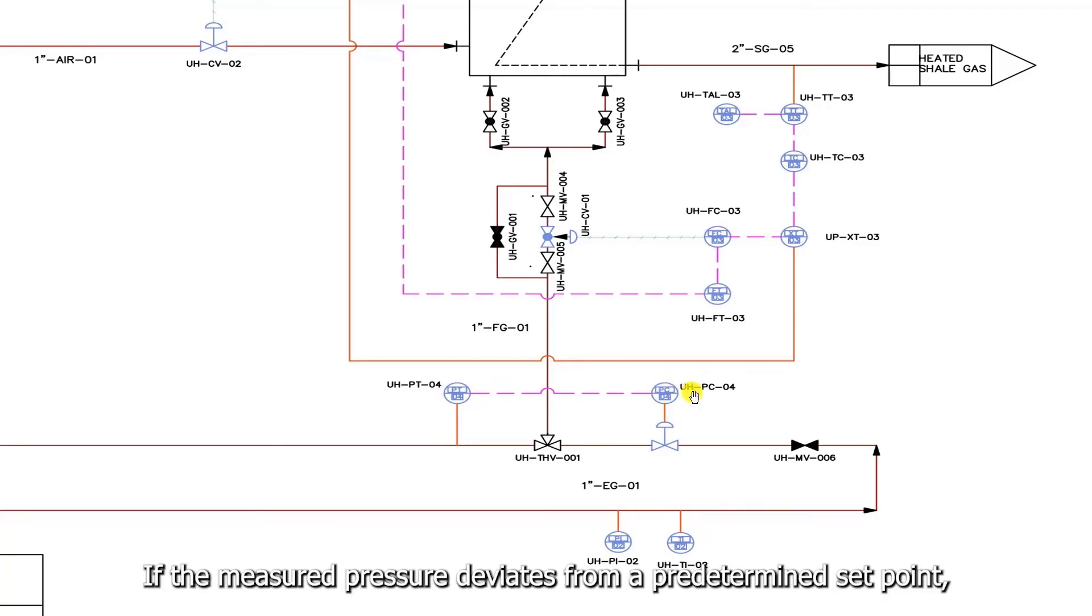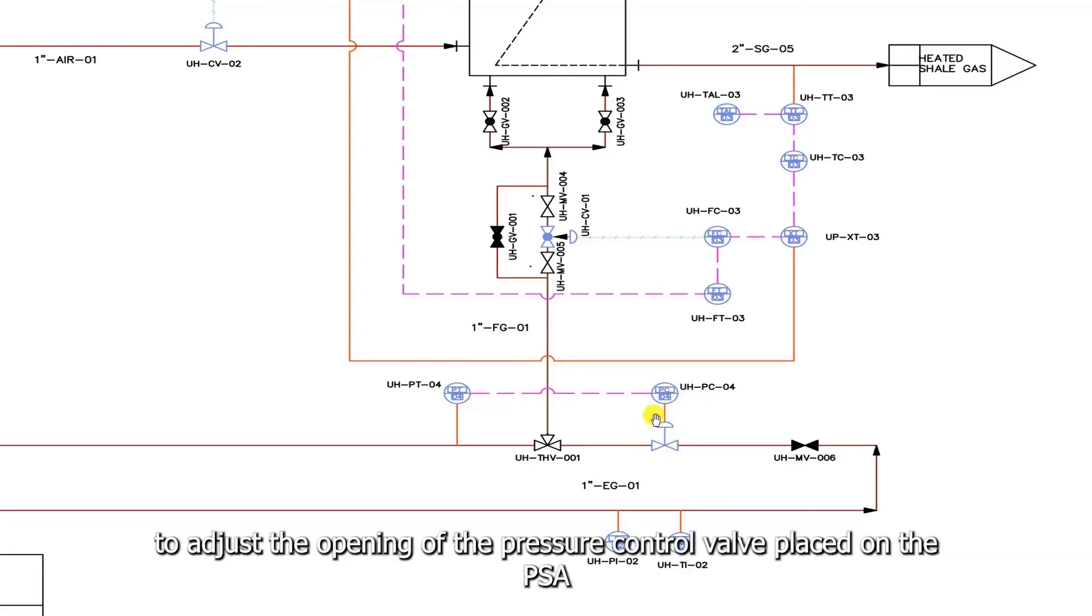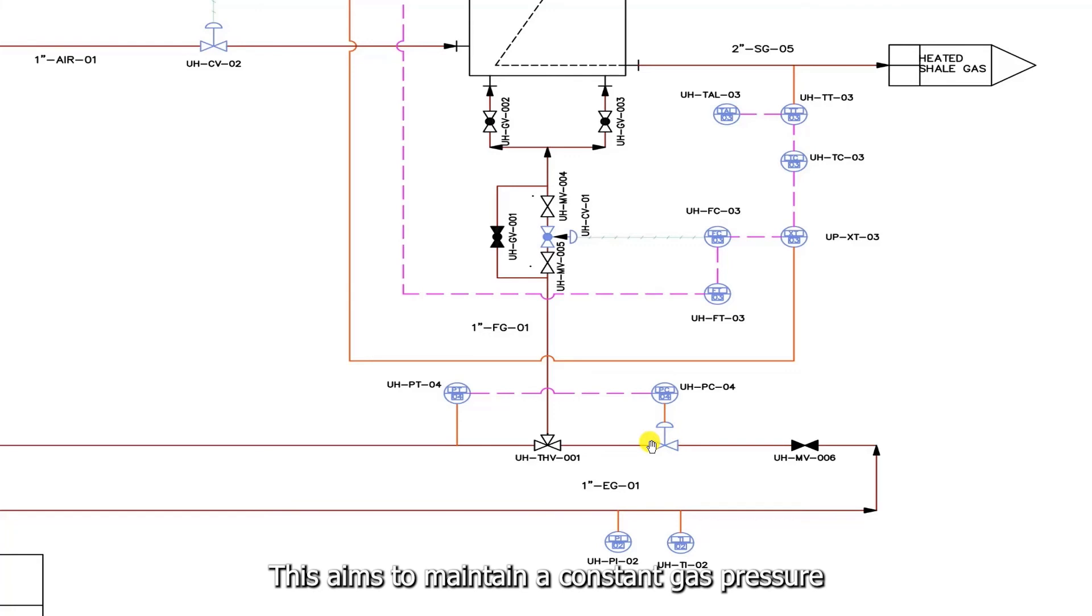The transmitter then sends the pressure measurement to a pressure controller. If the measured pressure deviates from a predetermined set point, the pressure controller will trigger a control signal to adjust the opening of the pressure control valve placed on the PSA exhaust gas. This aims to maintain a constant gas pressure supplied to the burners. Now, as pressure and flow are interrelated, a constant gas pressure is also equivalent to a constant gas flow.